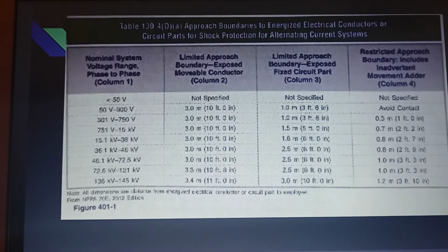And in this chart, it gives you the limited approach boundaries for a movable conductor, limited approach boundaries for a fixed circuit part, and also the restricted approach boundary. I'm not going to read all of them, but we'll do one of them. So we'll do 50 volts to 300 volts. The limited approach boundary for a movable conductor is 3 meters or 10 feet away. The limited approach boundary exposed for a fixed circuit part is 1 meter or 3 feet 6 inches. And then the restricted approach boundary for that is 0.3 meters, which is 1 foot. Actually, I lied. It is actually avoid contact. Sorry, it was a little hard to read.